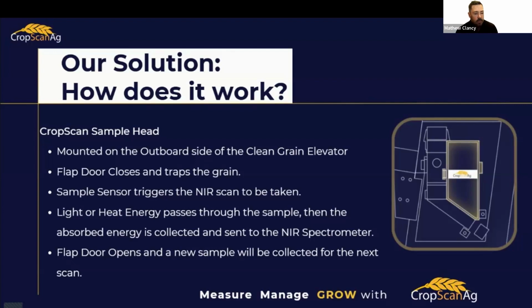Once those seeds are illuminated, it's really the heat energy exciting the seeds, and the molecules within the seeds are actually vibrating and oscillating. And that's what we're really measuring. We're measuring the absorption of energy on the seeds. And that's collected through the fiber and then sent back to the NIR spectrometer box. Okay. But really, what we're trying to do here is make sure we've got the probe in the right spot. That is key. That is CropScan 101.